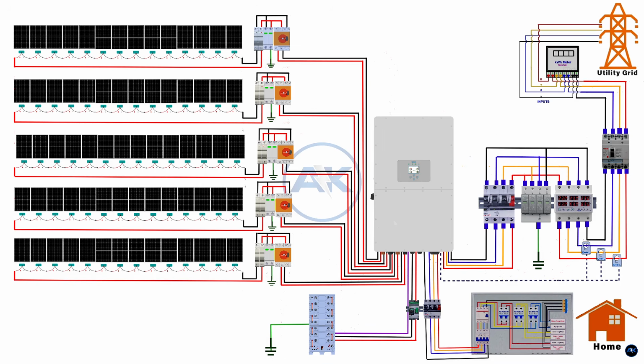Repeat the same process for phase L2 and phase L3. Ensure all CTs face the same direction and are fully closed. After installing the CT clamps, connect the CT signal cable to the energy meter or directly to the inverter depending on the system design. Match the CT inputs correctly for L1, L2, and L3. Do not extend the CT cable unless the manufacturer allows it. Secure the CT cables neatly and keep them away from high-voltage power cables to avoid interference. Once connected, the inverter will use CT measurements to continuously monitor grid power flow and automatically limit export to zero. This completes the CT installation for zero grid export control.